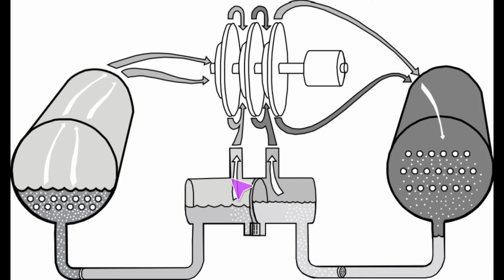This pulls into the economizer on the second stage impeller on this other tank. And again, it's the same scenario. Flash gas sits up here, liquid refrigerant gets even more subcooled. So we gain subcooling here on this liquid refrigerant. We gain even more subcooling here on this liquid refrigerant, and then it comes back out 100% liquid, going to the third stage of flash on the final plate going into the evaporator.